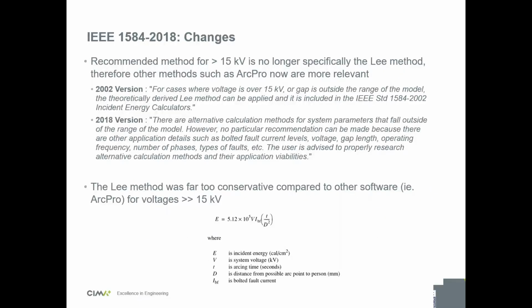What about arc flash for high voltage? Basically the IEEE, the last version, the 2002 version, said that above 15 kV, the Lee method was recommended. The Lee method is a pretty simple calculation, and it gives very conservative results. So instead of stating use the Lee method, they remove the Lee method from the standard, and then they say there are alternative ways. We don't recommend any one of them. So it gives more space to software solutions, other software solutions that can do high voltage arc flash, for example.